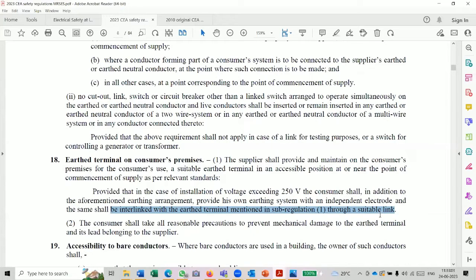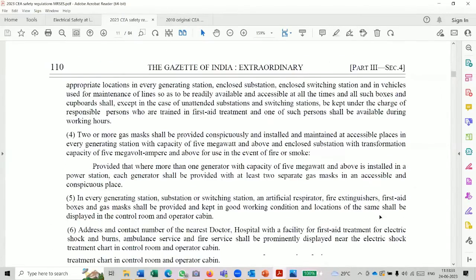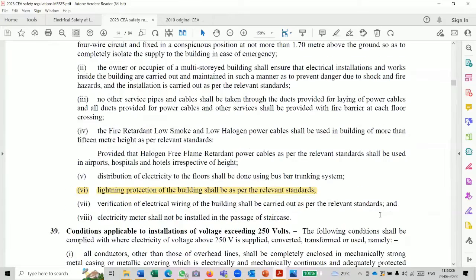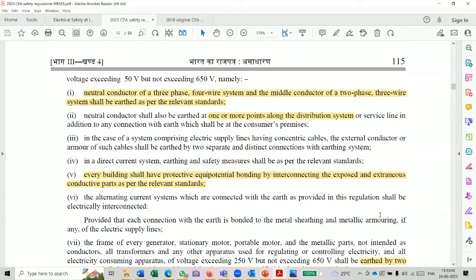I can see within the same distribution circle of the same DISCOM, they adopt a TT system, they adopt a TNC, and TNC plus TT. So something is confusing. The construction people don't know what is the responsibility of the DISCOM. It is a responsibility of the DISCOM as per regulation 43.2. You can refer to that 43.2 in the slide for the audience. Regulation 43.2 says the neutral conductor shall also be earthed at one or more points along the distribution system or service line, in addition to any connection with the earth which shall be at the consumer's premises.